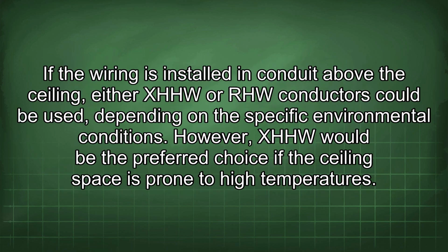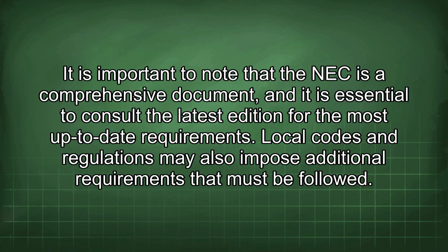If the wiring is installed in conduit above the ceiling, either XHHW or RHW conductors could be used depending on the specific environmental conditions. However, XHHW would be the preferred choice if the ceiling space is prone to high temperatures. It is important to note that the NEC is a comprehensive document, and it is essential to consult the latest edition for the most up-to-date requirements.